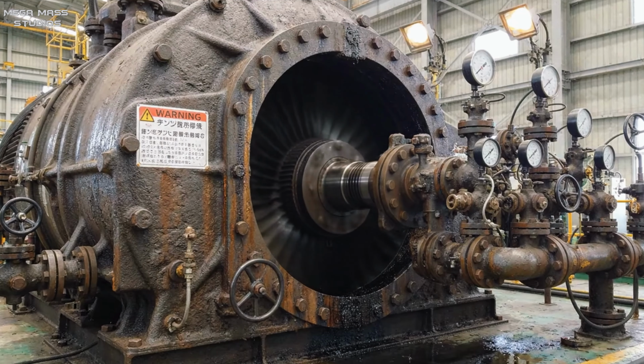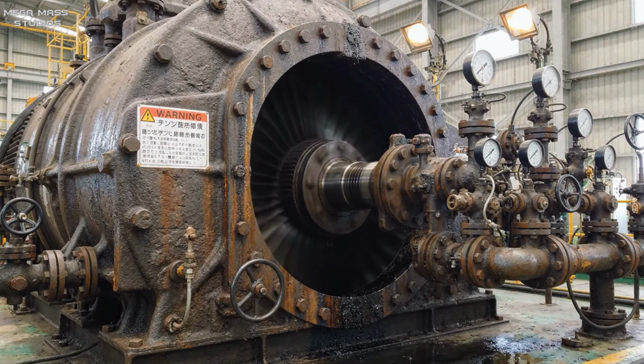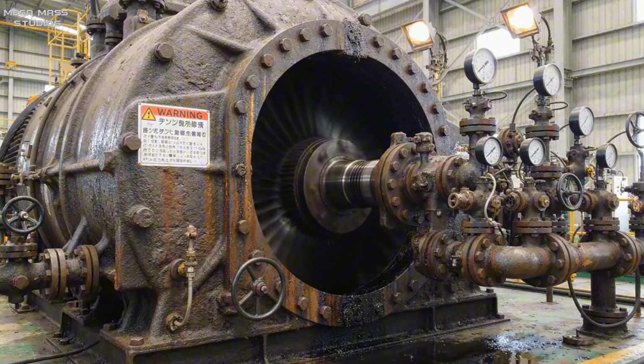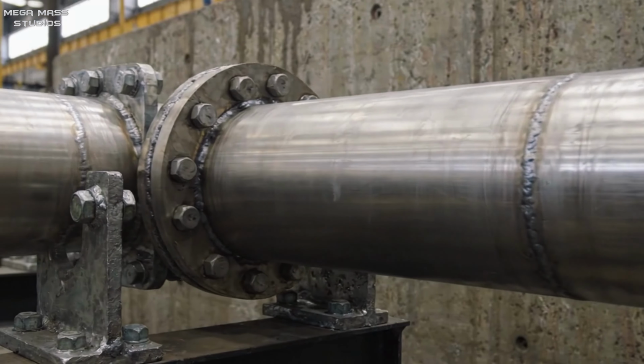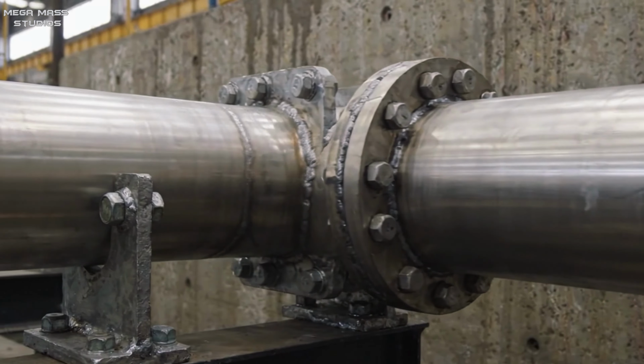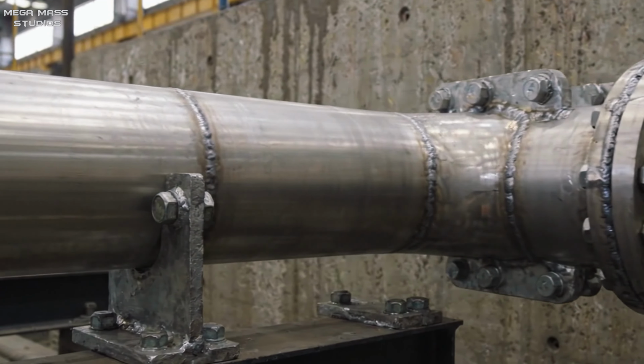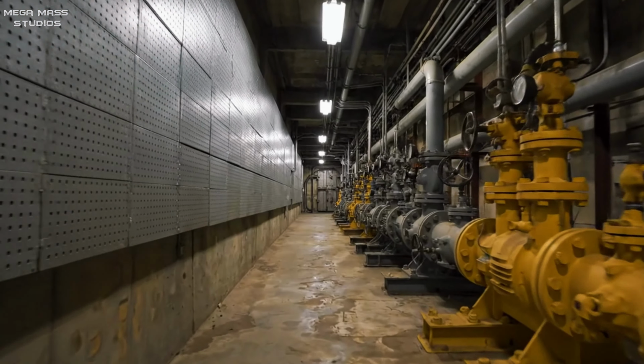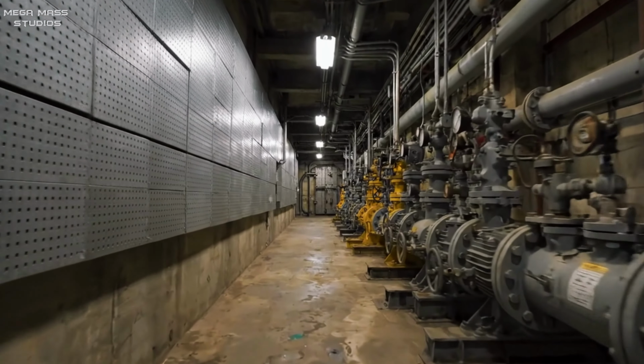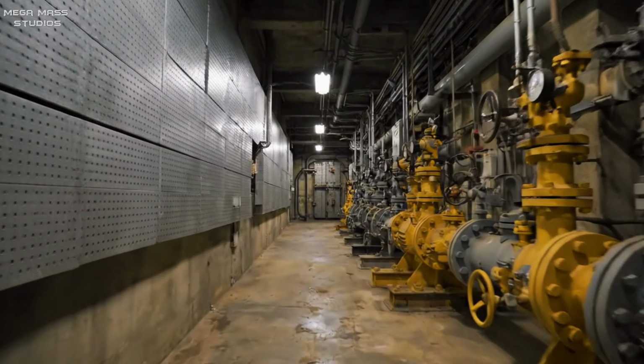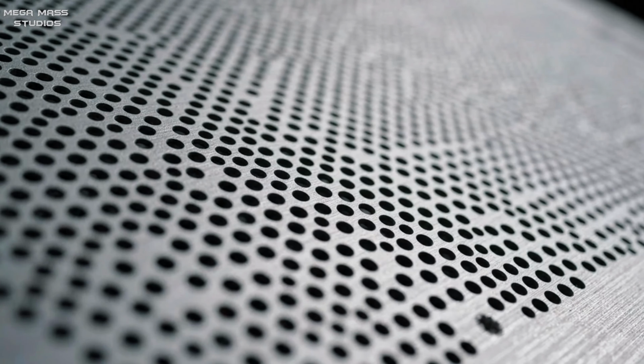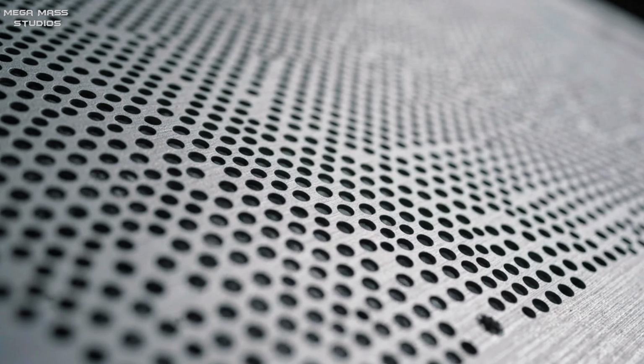The entire rotating assembly is enclosed in a thick, sound-insulating cast steel shroud to protect operators. High-decibel acoustic energy from the turbine can cause severe structural fatigue in nearby piping systems. Standing next to the colossal steel shroud of the CX400 turbine, we can feel the power driving this facility's operations. To absorb these extreme sound waves, the walls of the pump room are covered in acoustic panels. These metal panels feature micro-perforations, designed to trap and dissipate high-frequency sound energy safely.